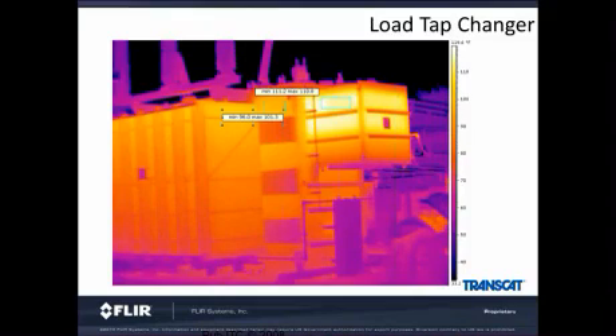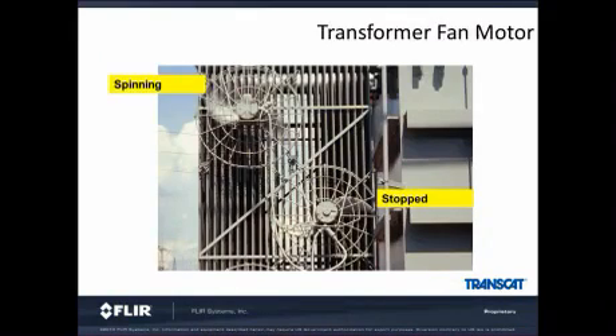The load tap changer in this picture should always be the same temperature or cooler than the transformer. As we can see in this picture, the load tap changer is much hotter, and that is a major concern. In fact, that load tap changer is about 17 degrees warmer than the transformer. One nice tool in the infrared camera is the Area Max box, and this tool on the camera allows you to quickly ascertain what the max temperature is. This makes it easy to find out how hot your target actually is.